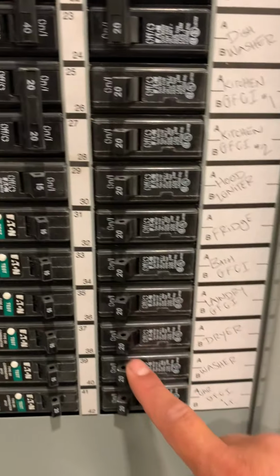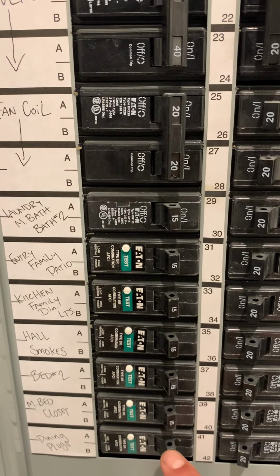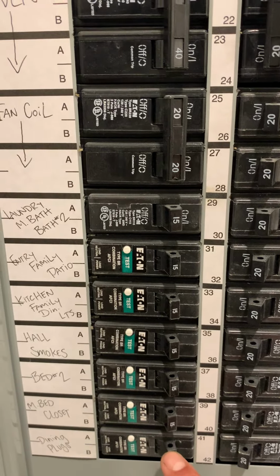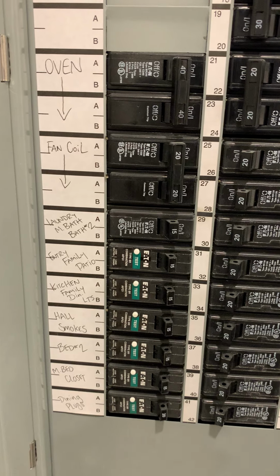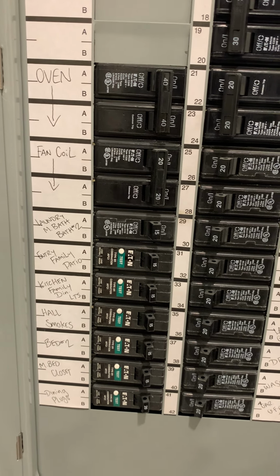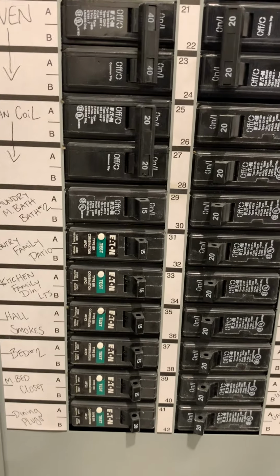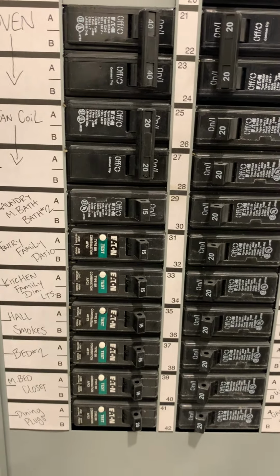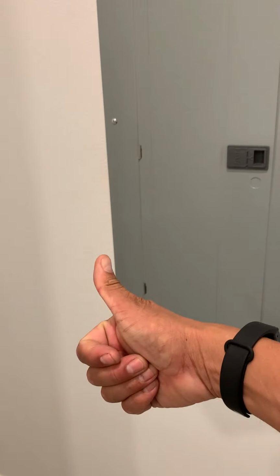These are all your 20 amps, and then we have 15 amps—these are the arc faults for the bedrooms and whatnot. So basically you want to use the 20 amp outlets for things like vacuuming, because if you plug too many things into a 15 amp it'll just keep popping. Vacuums might say they only pull about 11 amps, but when the engine whirls up it jumps to about 15, and once the motor gets running it goes down to the normal running amperage.